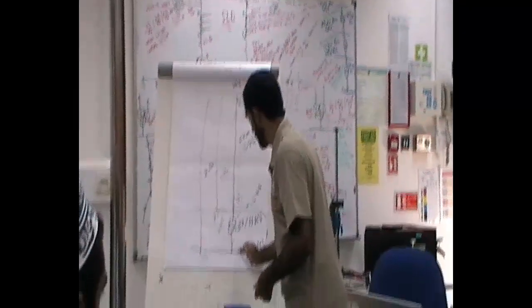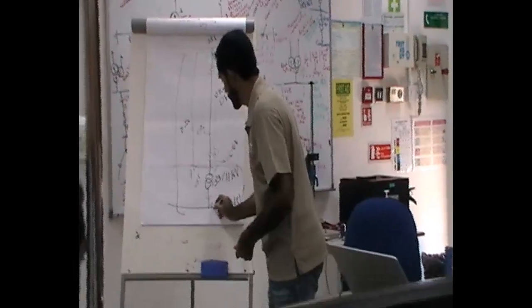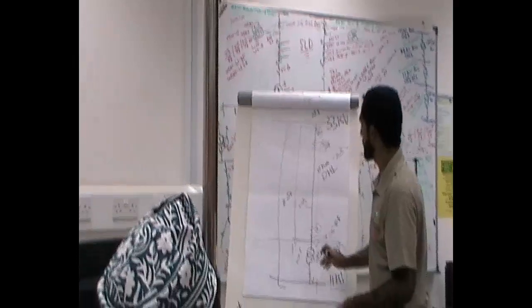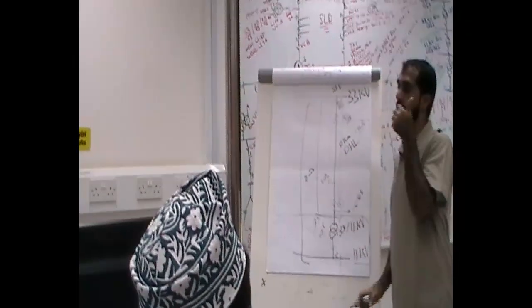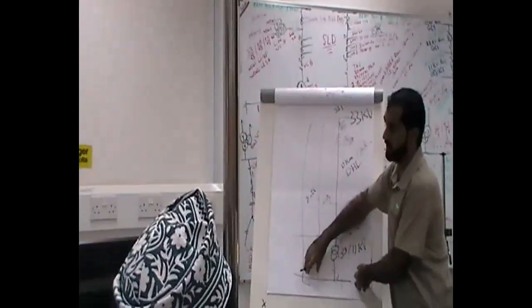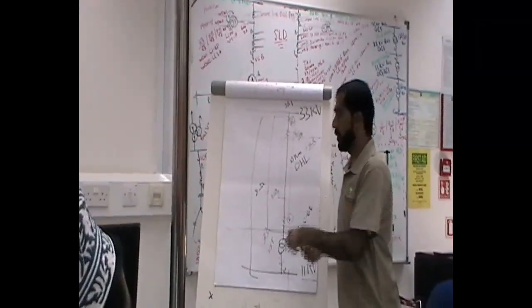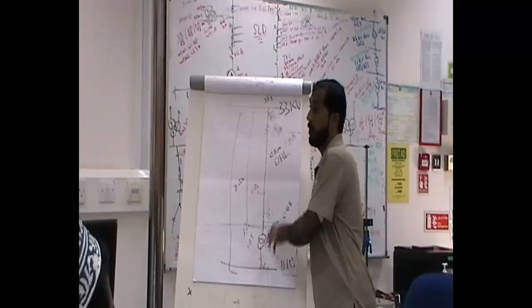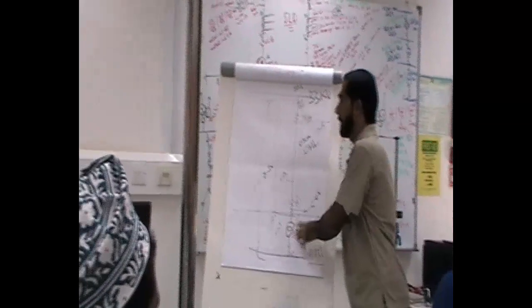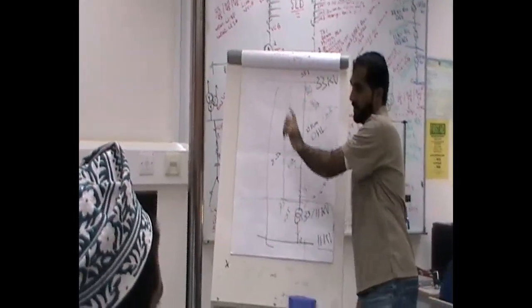Assuming the fault is here in the element, I have overcurrent relay in the outgoing feeder. If I have bus section, I have another overcurrent relay. I have the incomer, transformer incomer protection. So basically, I don't expect zone 3 to operate except in one case: whenever the whole protection system is off in this substation. In this case, only zone 3 will operate. And this is what happened. Usually, we lose the whole auxiliary supply, so all relays will be off. Nothing will work in this substation. The backup is zone 1. So, sorry, zone 3. The backup is zone 3.